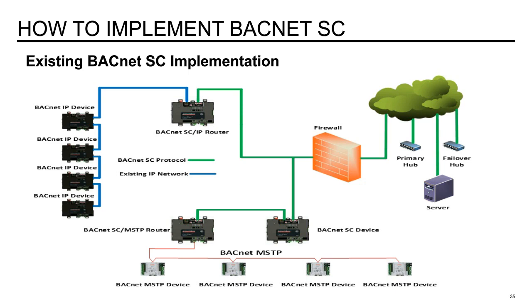Next question from Claude Novauer. When will BACnet SC be fully approved and implemented? As it stands right now, BACnet SC is approved. It was an addendum that was issued to the BACnet standard in November of last year, so it is an approved protocol. Manufacturers are now adopting the SC protocol into their devices and solutions, and that's one of the reasons for the early adoption acceleration program that BACnet is hosting, to drive this implementation and get it to the market quicker.